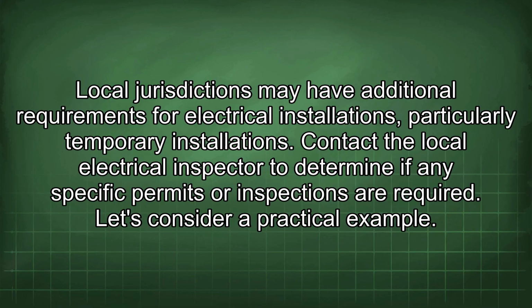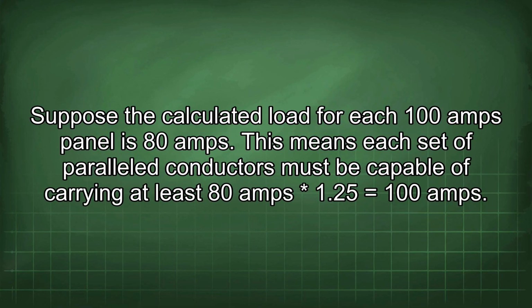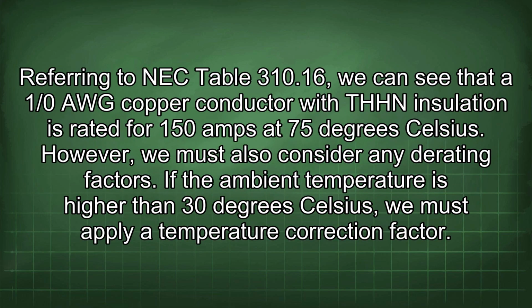Let's consider a practical example. Suppose the calculated load for each 100 amps panel is 80 amps. This means each set of paralleled conductors must be capable of carrying at least 80 amps * 1.25 equals 100 amps. Referring to NEC Table 310.16, we can see that a 1/0 AWG copper conductor with THHN insulation is rated for 150 amps at 75 degrees Celsius.